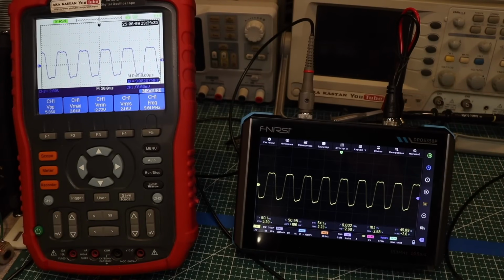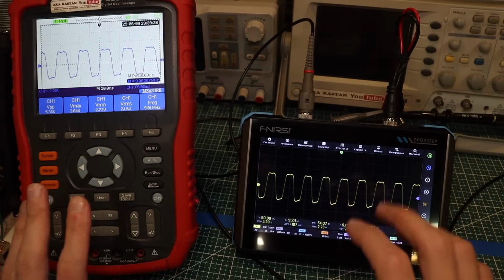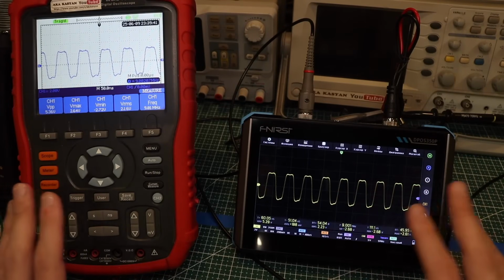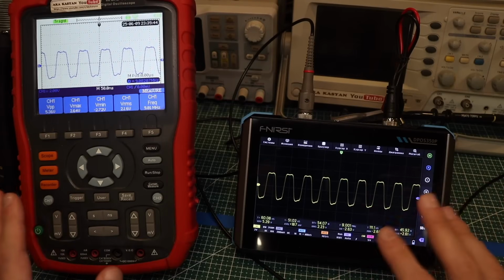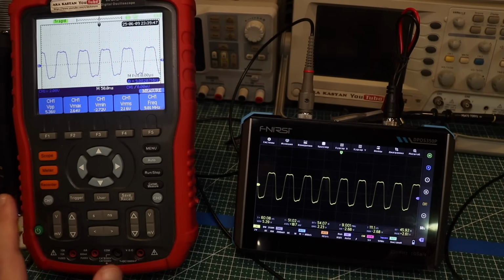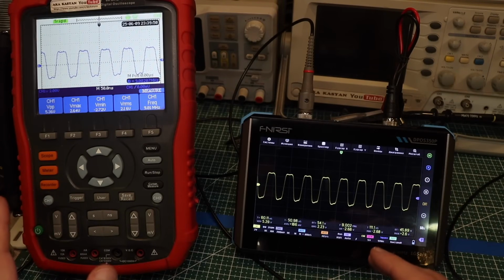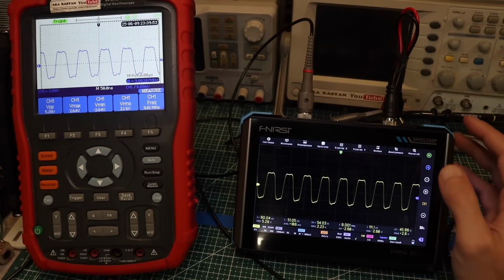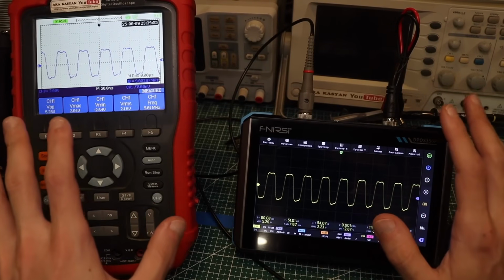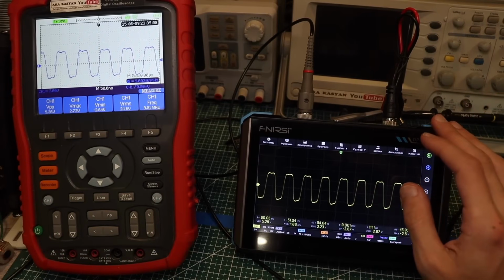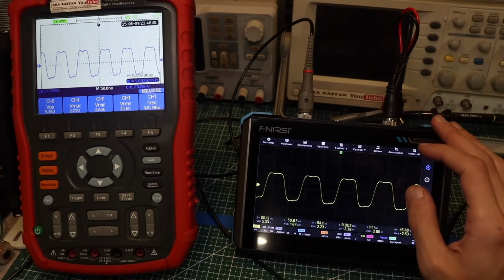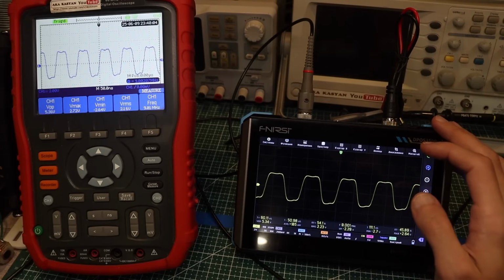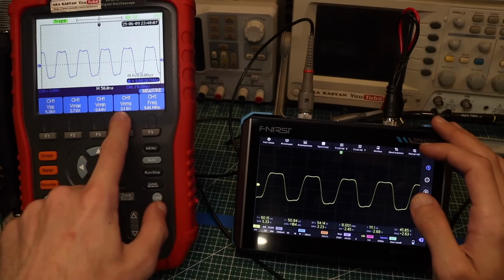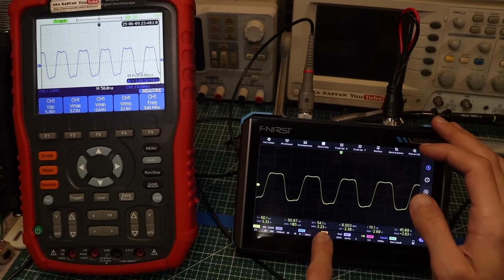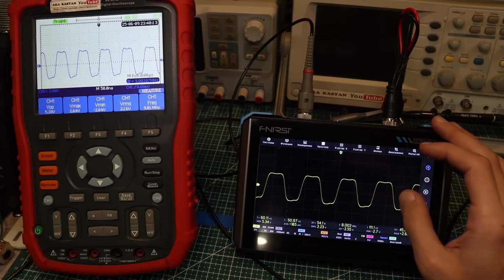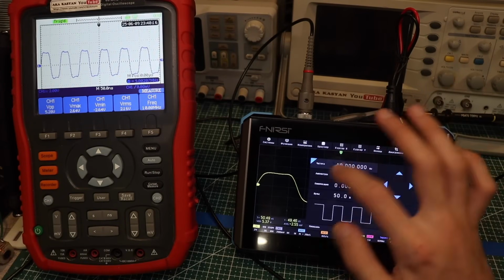It's important to understand that even with very similar settings and the same sampling rate, the devices can operate at different speeds in certain modes. One device might pick up interference or a spike that the other doesn't notice. That's normal since these aren't identical devices, though even identical devices can behave this way, so we don't pay much attention to it. The RMS value is a bit understated, and the FNIRSI also picks up on this. Everything's fine, we'll set the maximum to 10 megahertz.